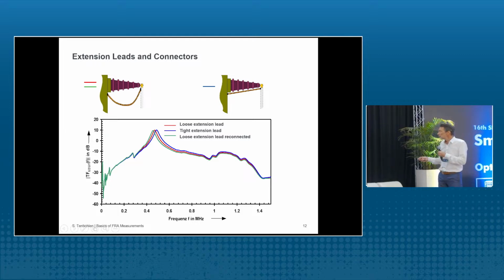So if you do the measurement like this, and the next time you do it, maybe the loop is a little bit bigger or a little bit smaller, you are changing the inductance of the measurement, and therefore also the frequency response. And then you have two different curves, and you have to decide: is the difference because of a failure inside the transformer, or is it because this loop is different? Therefore it is strongly recommended to have such a tight grounding strip. This is one thing which you have to consider in measuring an FRA.